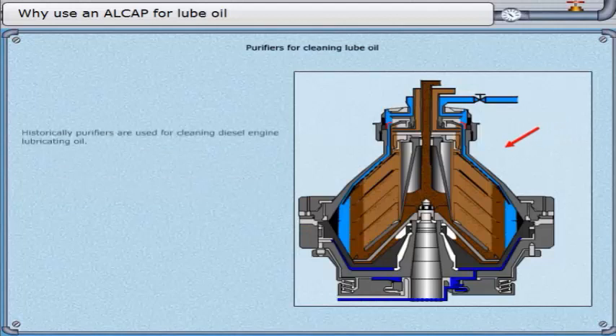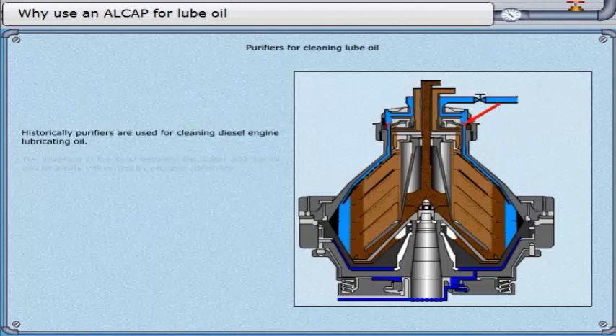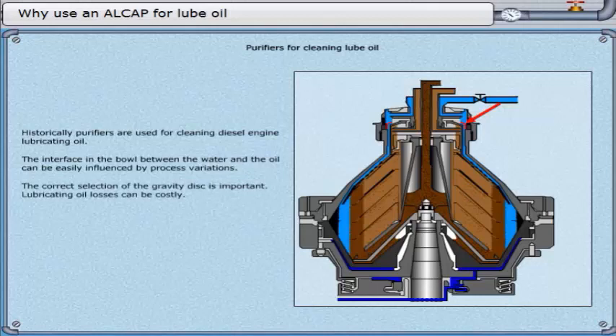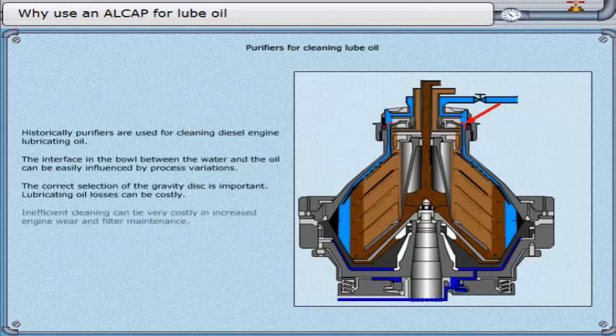Historically, purifiers are used for cleaning diesel engine lubricating oil. The interface in the bowl between the water and the oil can be easily influenced by process variations. The correct selection of the gravity disk is important, and lubricating oil losses can be costly. Inefficient cleaning can also be very costly in terms of increased engine wear and filter maintenance.